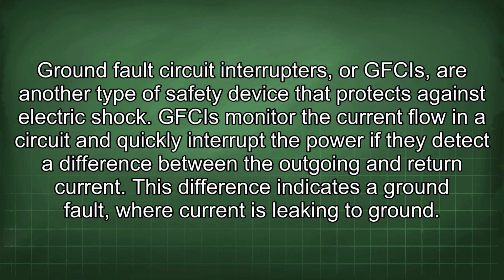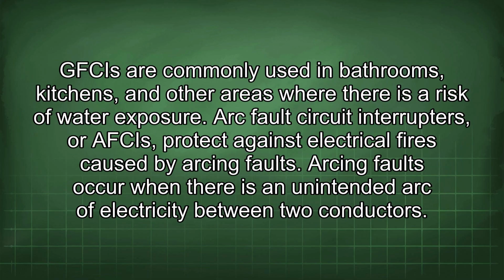Ground fault circuit interrupters, or GFCIs, are another type of safety device that protects against electric shock. GFCIs monitor the current flow in a circuit and quickly interrupt the power if they detect a difference between the outgoing and return current. This difference indicates a ground fault, where current is leaking to ground. GFCIs are commonly used in bathrooms, kitchens, and other areas where there is a risk of water exposure.